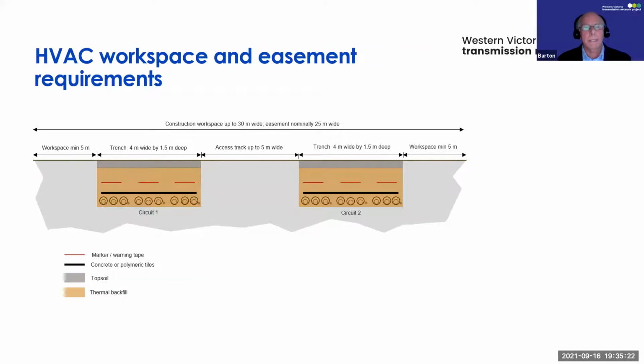This is a typical cross section of what an easement and workspace looks like. You can see the two trenches, and the orange colour is thermal backfill, applied around the cables to help dissipate heat as they transfer energy. A transmission line dissipates heat into the air, which also insulates the conductors, whereas underground cables need to be heavily insulated, which is why they are much bigger in cross-section than overhead wires. The two trenches are separated due to the thermal performance of the cables.